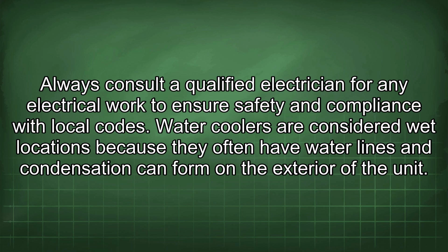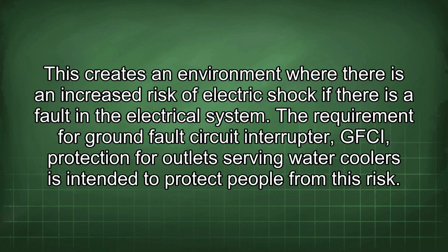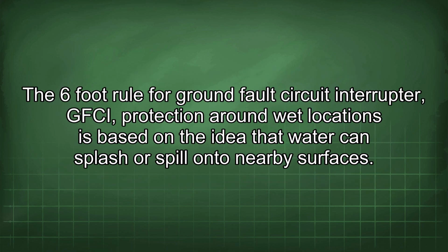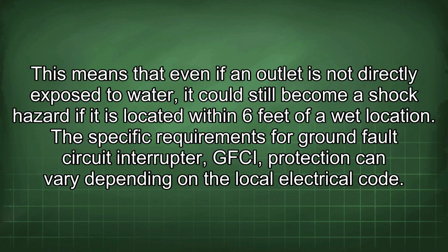Water coolers are considered wet locations because they often have water lines and condensation can form on the exterior of the unit. This creates an environment where there is an increased risk of electric shock if there is a fault in the electrical system. The requirement for GFCI protection for outlets serving water coolers is intended to protect people from this risk. The 6-foot rule for GFCI protection around wet locations is based on the idea that water can splash or spill onto nearby surfaces. This means that even if an outlet is not directly exposed to water, it can still become a shock hazard if it is located within 6 feet of a wet location.